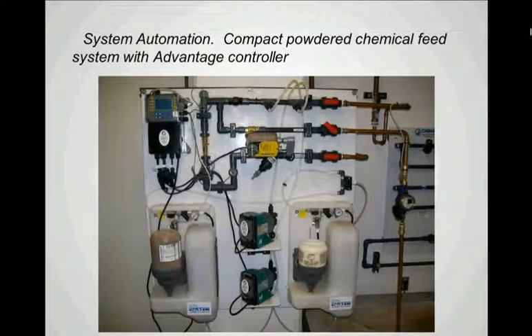Now here's another configuration for an automated system. Here once again we see an Advantage controller. We see the sample loops here for the water samples coming in and chemical injection points. But in this design we use a solid chemical in a smaller container. So it's a different method, different feed system that's designed to minimize the handling and storing of liquid chemicals in large 30 or 55 gallon drums. So in some applications this has merit over the more traditional larger chemical feed systems for the bigger cooling towers.